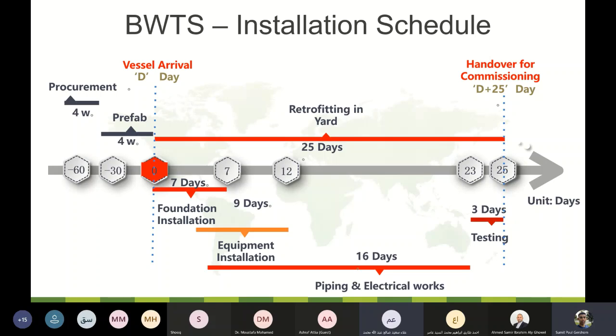In those big projects, we start procurement 60 days ahead, then take a minus-30, one month period for prefabrication of all pipes, foundations, cable trays, and electrical panel foundations. Then at day 0, we have 7 days of foundation installation for both electrical and mechanical equipment. From day 7 to day 12 we focus on equipment installation, and in parallel we start piping and electrical works. The last 3 days are kept for pre-commissioning and commissioning.